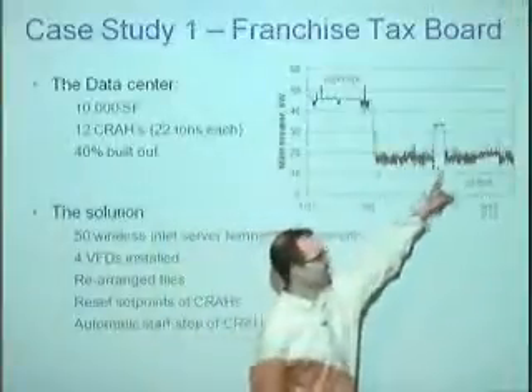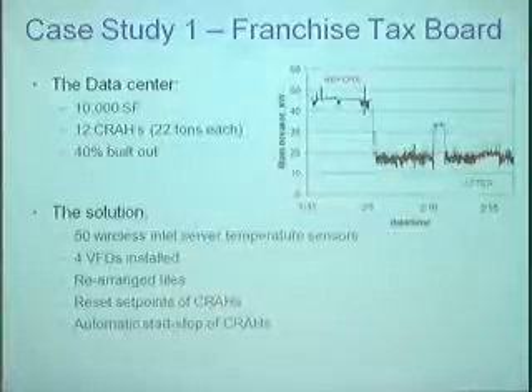You can see this is when we turned it on. They had a bunch of alarms based on relative humidity, and if you raise your temperature, your relative humidity goes down. So they had to turn on their humidifiers for a little while to get their relative humidity back up, which is kind of an interesting story of how much energy humidification actually uses.